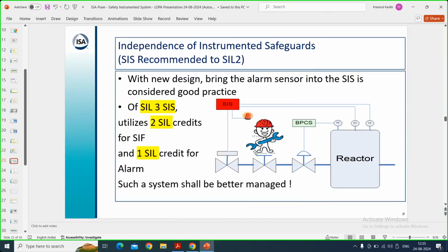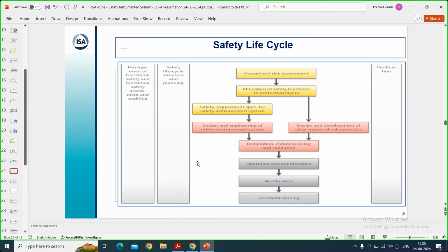require SIL or not. So HAZOP and risk assessment is the first stage where you decide whether you need SIL or not. Now, all the process loops do not require SIL. Only a few process loops may require SIL. And if you are not handling any flammable or hazardous toxic chemicals, maybe you don't require SIL, but that is to be decided at the first stage of the safety life cycle of SIS. Am I clear?